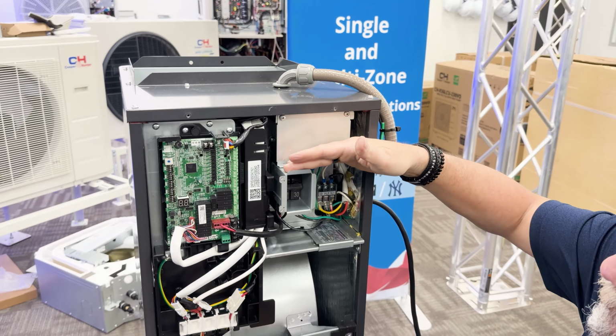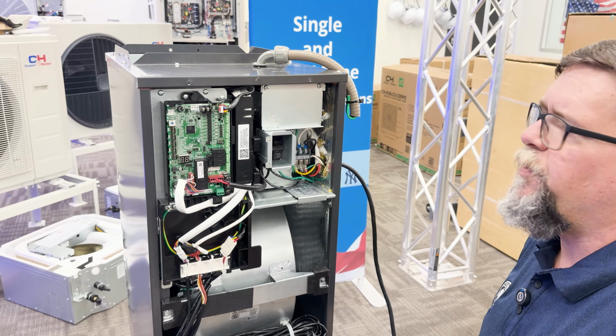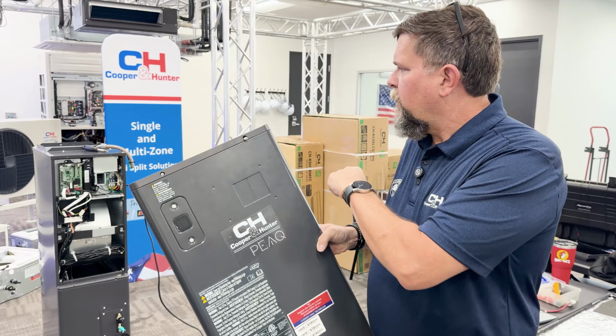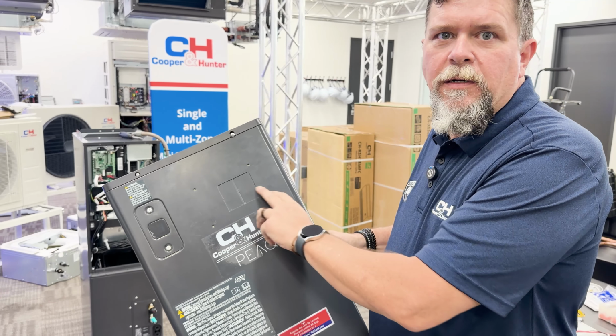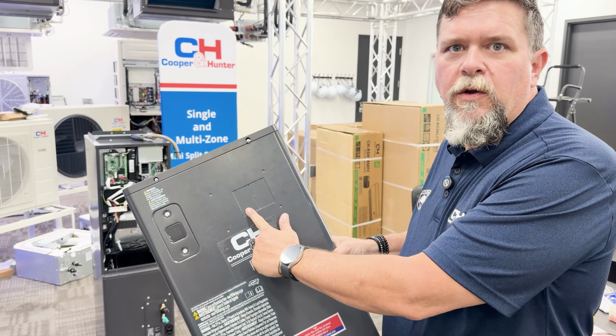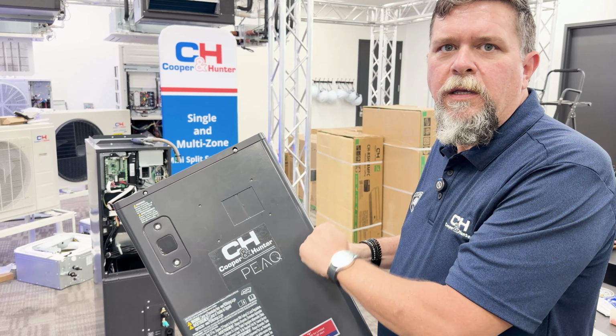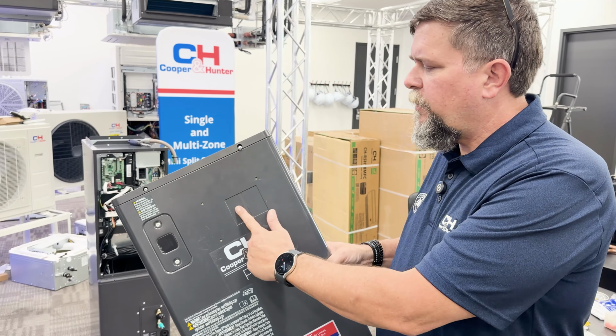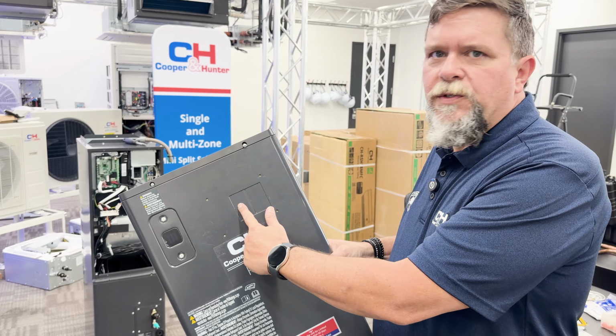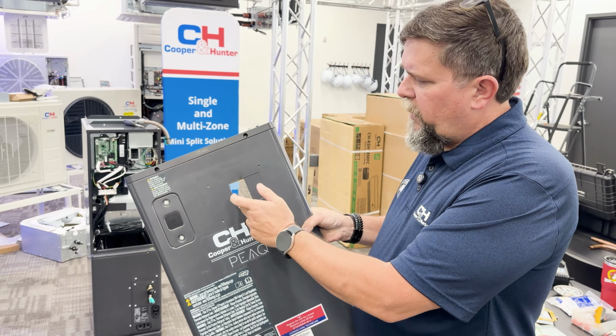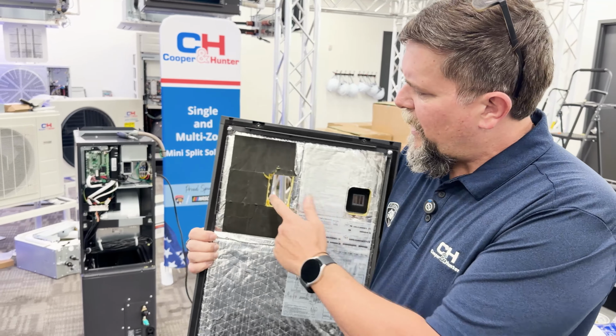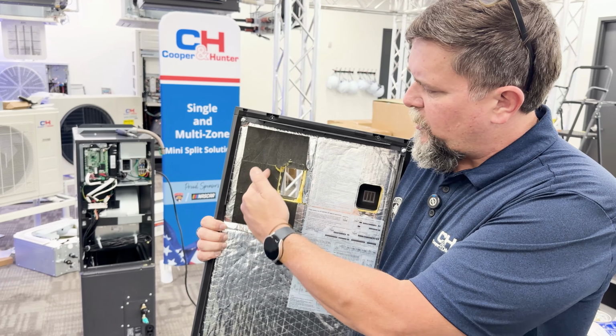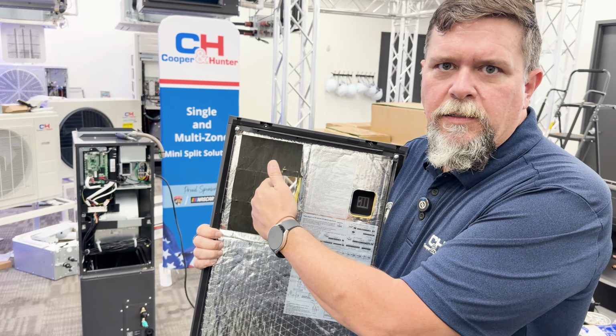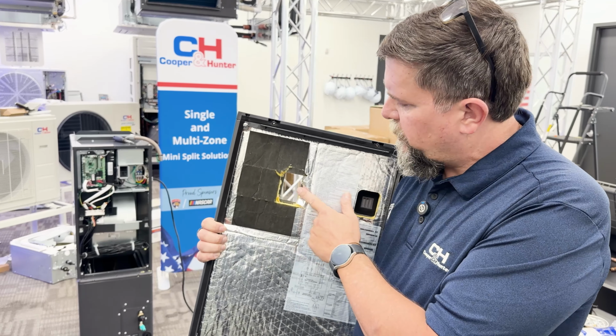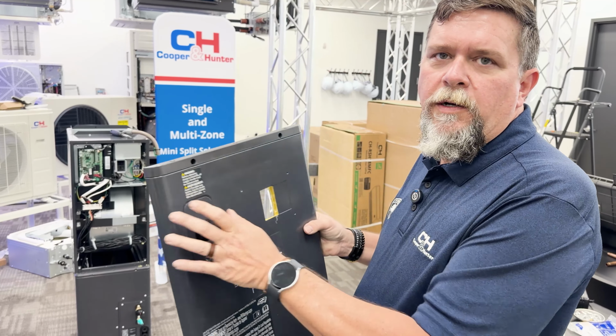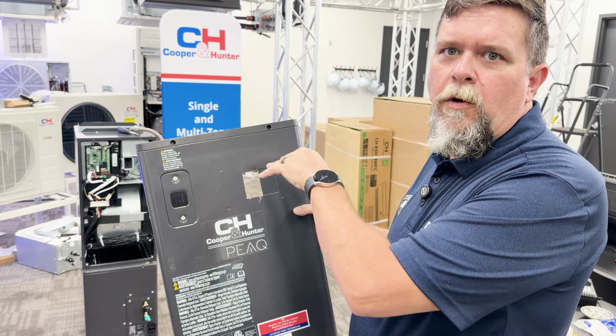Now we got our protective cover on here, and the next step is to put the door cover on. To prep the door for this, we got 2 knockouts here, and if you follow the instruction manual, it'll tell you which knockout to remove for which heater kit. In this instance, we're using the 5 kW, so we're gonna knock out the one on the left. With the knockout removed on the front side, you'll also see on the back side there's some insulation. It's actually perforated, so you can take a straight edge, knock that out, pull out the insulation to create our hole for the next step, putting the door over the circuit breaker.